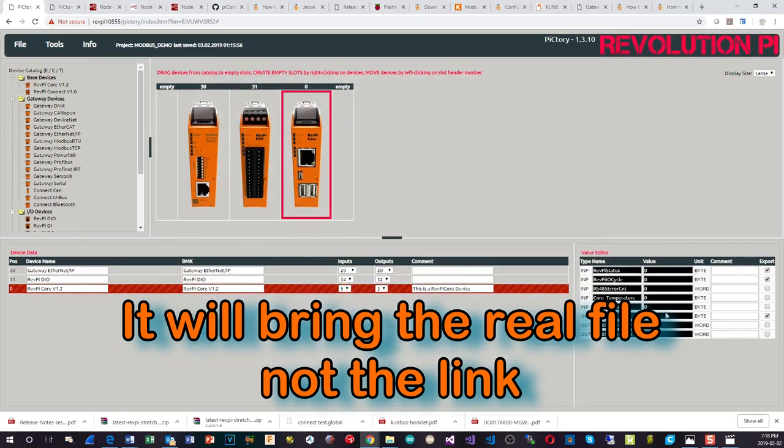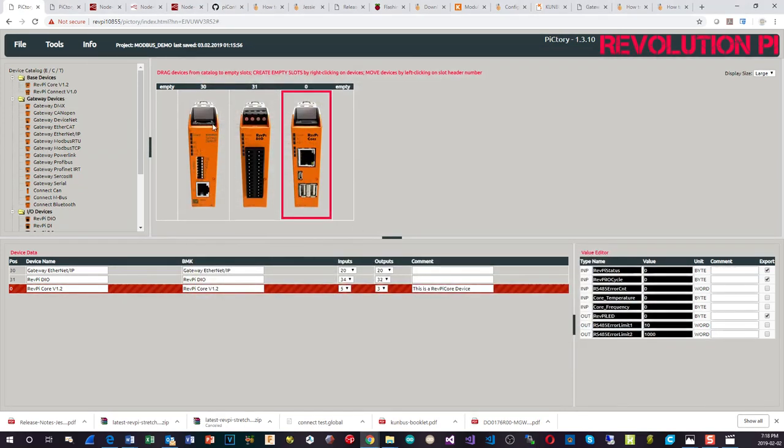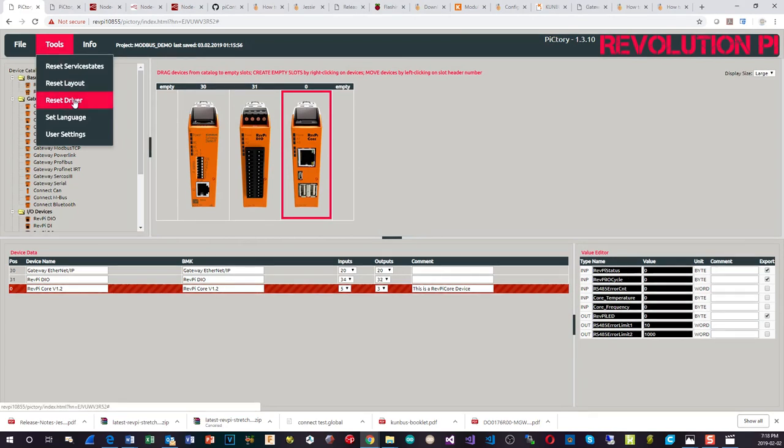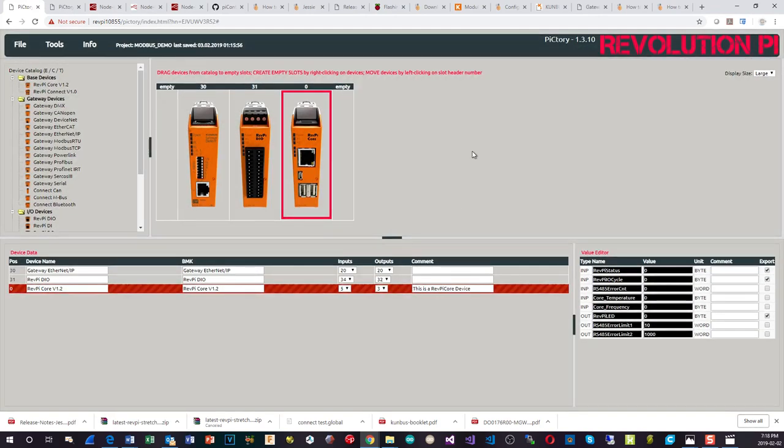When you do configure all of these changes, you want it to become part of the runtime. Right now it's just saved as a config file. What you would do is you go into tools and you would click on reset the driver. And once you do that, the internal kernel driver that deals with all of the IO will be rebooted. It'll read the new configuration, initialize all of the IO modules, and then everything will be up and running.